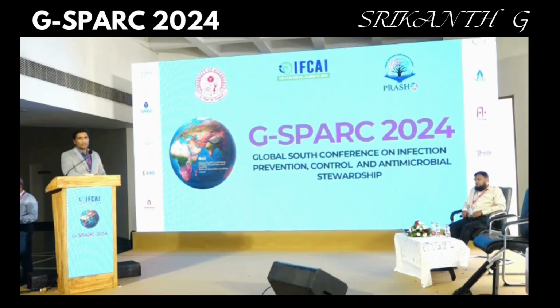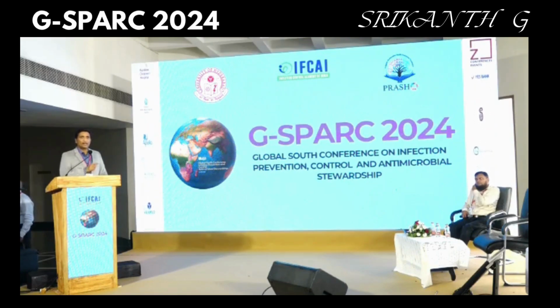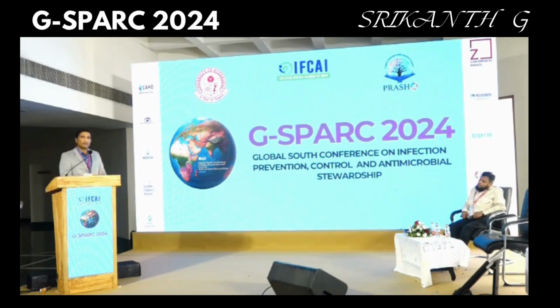Just using a medical bleach to clean the surface of the machine should be sufficient. At the end of every day, again, internal disinfection with citric acid, and at the end of every week, internal disinfection with a disinfectant like a medical bleach can be done.